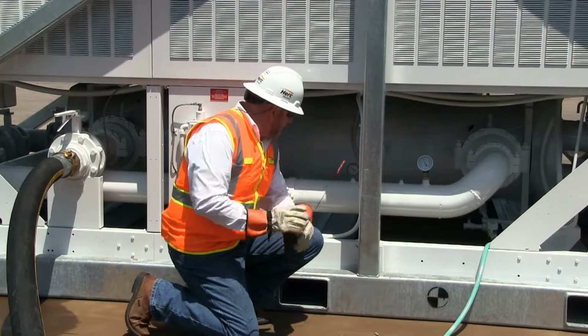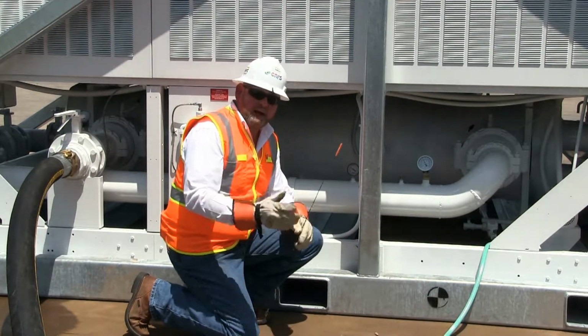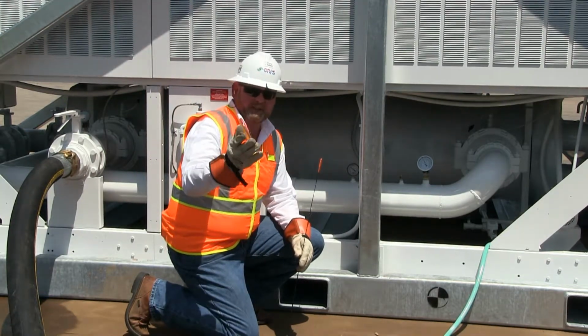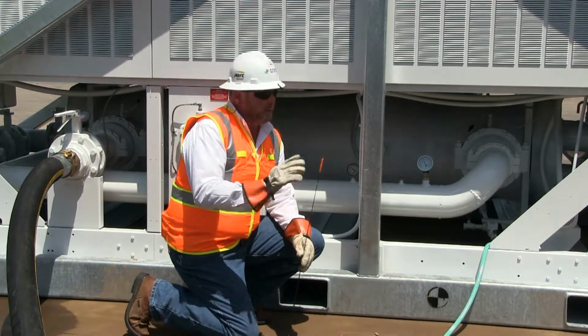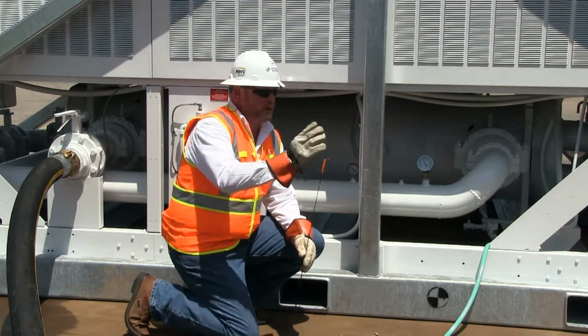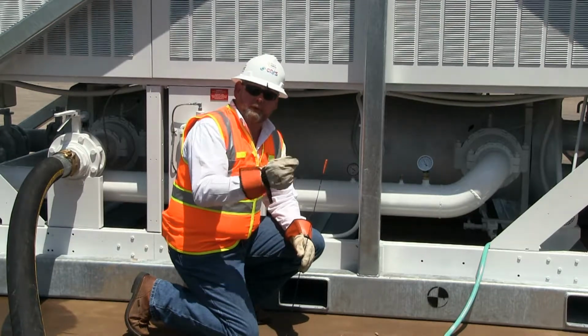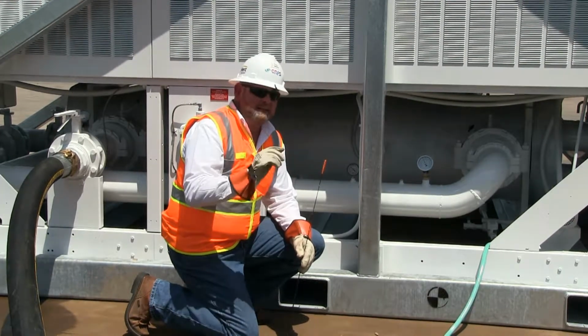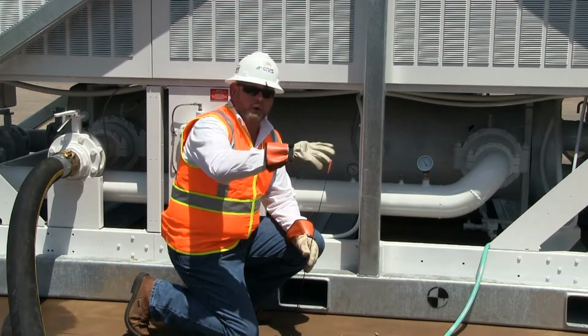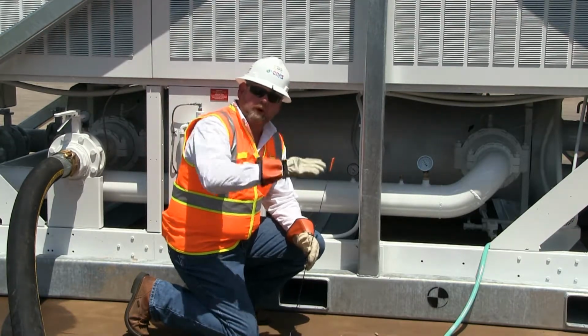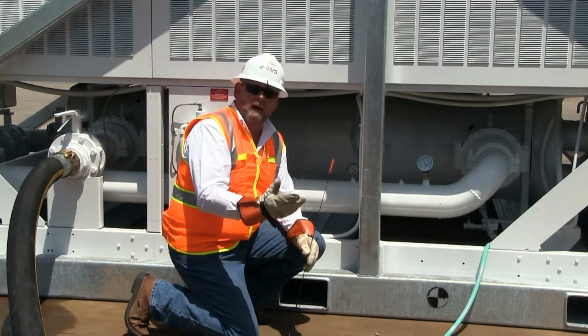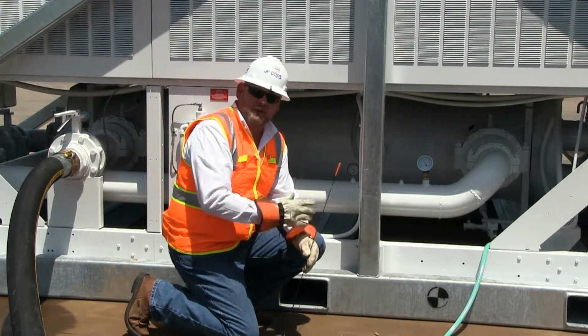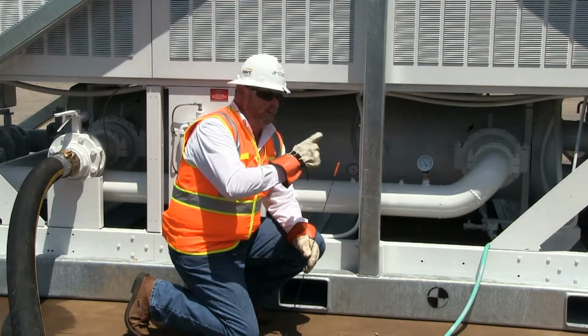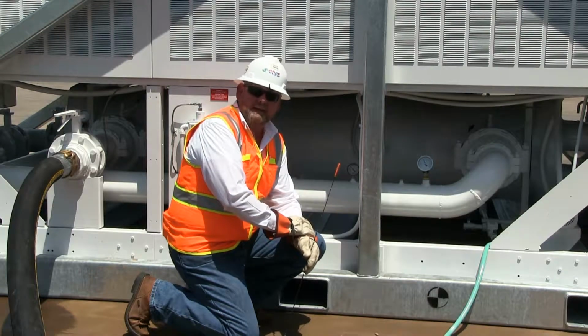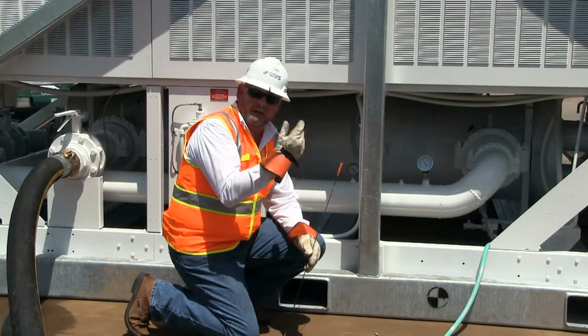Okay, we've got our system completely filled now. We're at about 45 psi according to our gauge here, which is fine. 40 to 55, 60 psi is a good starting point. We've already circulated the water through our hoses, our air handler, and our pump, and it went through a process of bleeding air. Every time we turn our pump on, we stir the water through the system. All the water falls down, all the air goes up, and we go to our high points and bleed out the air. Your high point is going to be on the chiller. There's a high point bleed on the other side, clearly labeled. You open it up and that'll pull the air off the top of the heat exchanger.